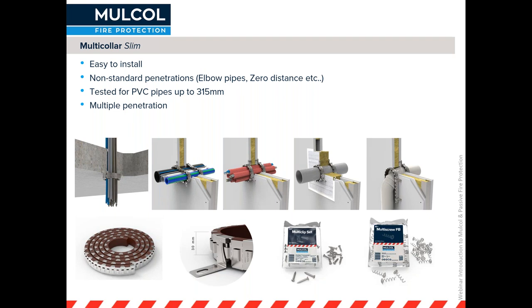Of course, we have tested it with our Multimastic C system, our coated board system, and you can see in the second picture from the right that it's been used with the coated board system, and there's no need to line the opening. You don't see a lining around the opening with plasterboard. It's just something I wanted to point out to you. When you use it with the coated board system, we've got a special Multiscrew FB, which is a little pigtail screw to fix the collar into the coated board.